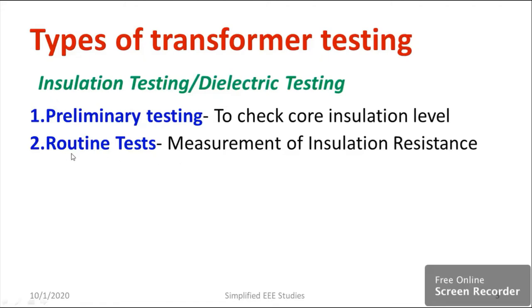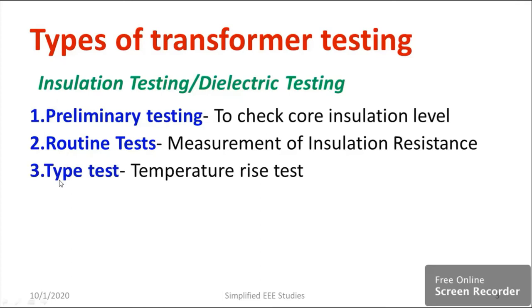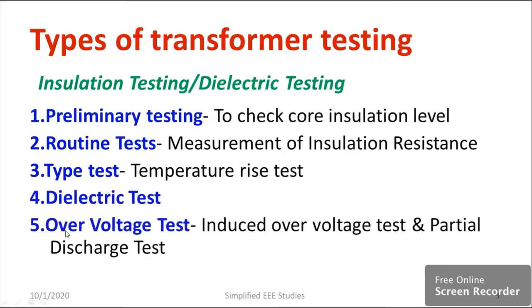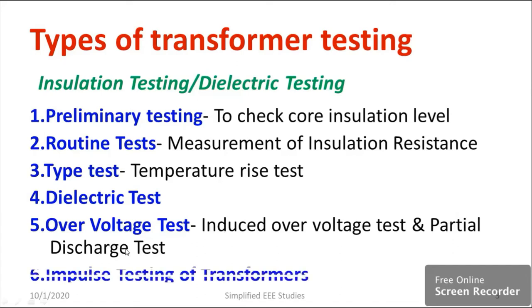The main purpose of the routine test is to check whether the insulation resistance is proper or not. If I talk about the type test, it is mainly used for temperature rise. Regarding dielectric test, there is also the overvoltage test. There are two types: induced overvoltage test and partial discharge test. Later we will be discussing impulse testing of transformers.